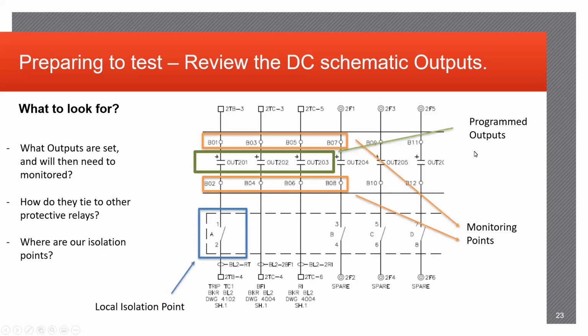Going into it a little bit further, monitoring your programmed outputs, the points that it may contact, and your local isolation point. Again, if these outputs aren't associated with a knife blade, as shown here on this BFI and RI, which stands for the breaker failure initiate and reclose initiate, you'll want to identify that these output contacts are isolated elsewhere and that there's no other way for this output to trigger an event. And then most likely what you'll need to do is either go to the back of the relay cabinet and hook up to the terminal blocks associated here with this 2 TC4 and 3, or just go straight to the relay and go to Bravo 3 and Bravo 4. Usually you just pick the point that it's easier to access.